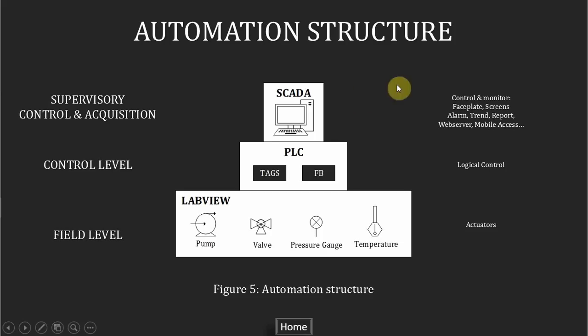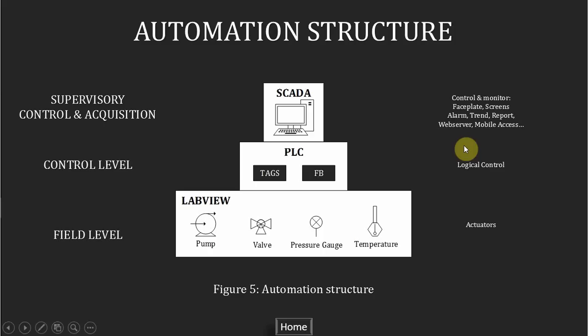Here is the figure of my automation structure. Actually above this also has the data server and plant management level, but in this study I only work on these three. In SCADA we have the screen and faceplates to control and monitor device and equipment, and some tools to access data such as alarm, trend or report. In control level we have PLC or RTUs, remote terminal units, to control and get data from the actuator in the field level.